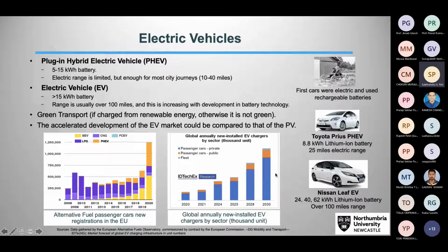Look here, significant increase in domestic chargers. Remember I mentioned earlier, the grid was designed with after-diversity maximum demand for houses being around 1.5 kilowatt. Now you are putting a charger in each house of at least 3 kilowatt rating - there are some domestic chargers at 7 kilowatt. So you are already doubling or tripling the demand in that house, which will have significant impact on the grid, as I'll show you in the next slides.